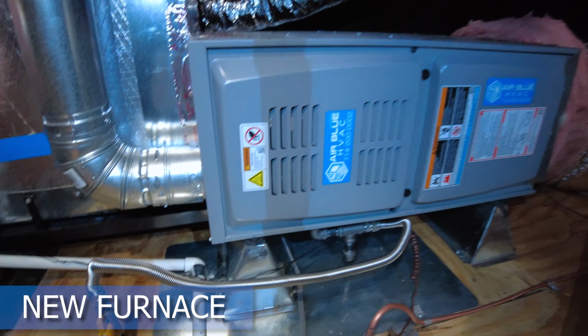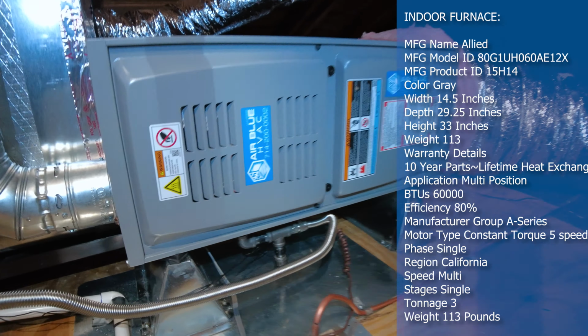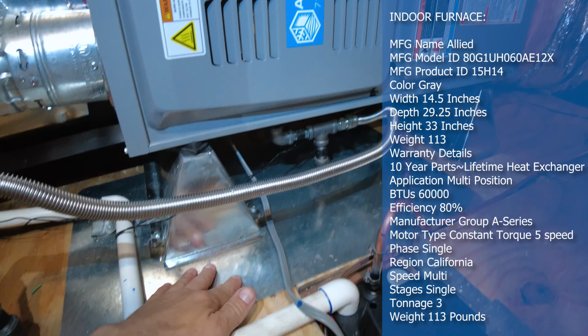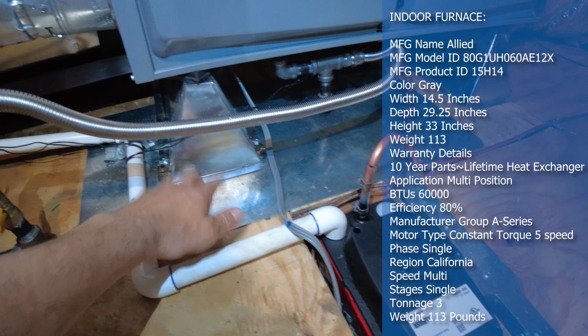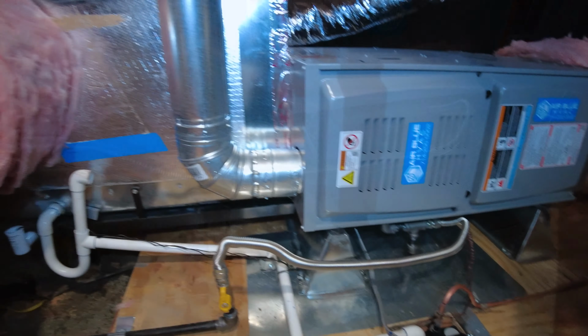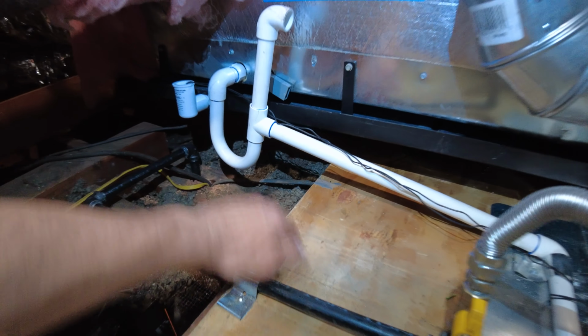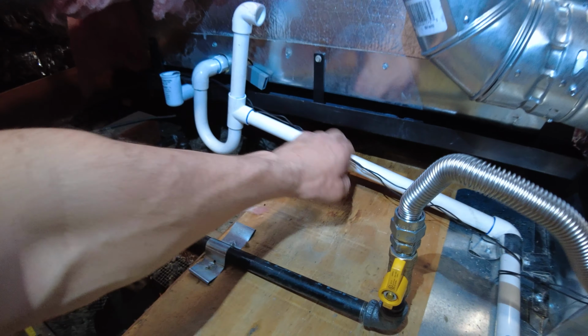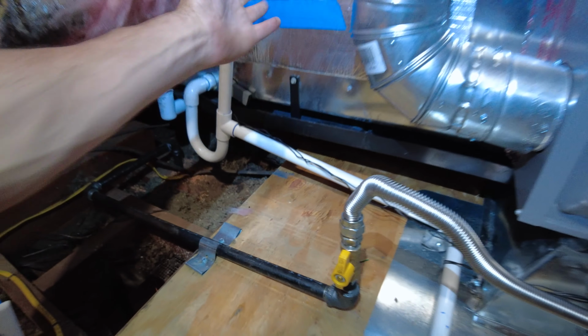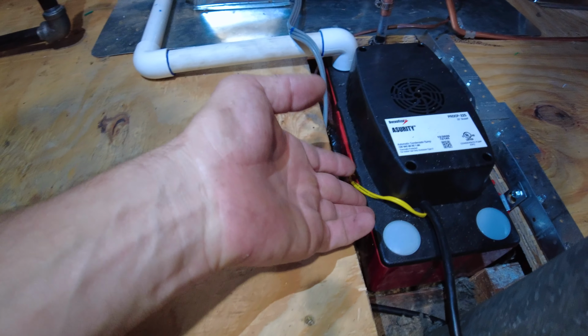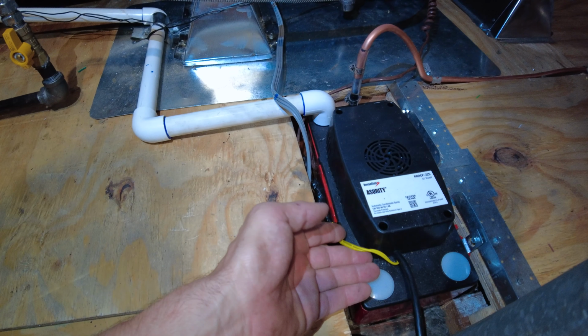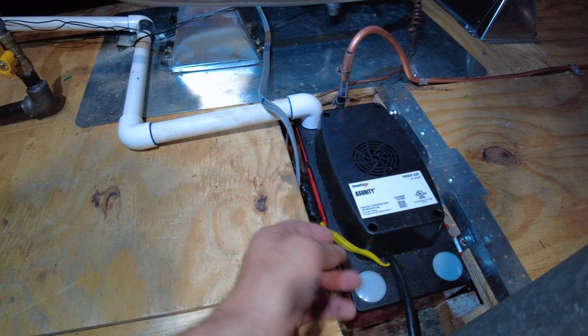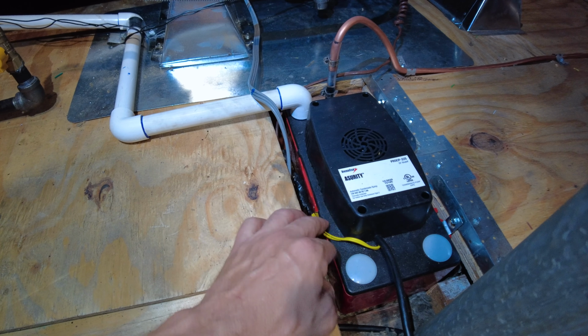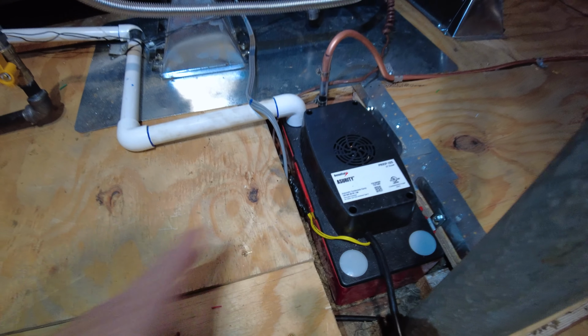This is our new furnace. We relocated it from the closet. The new furnace stands are metal. We put some sheet metal under the burners. We put rubber pads, a new evaporative coil, a secondary drain pan, and an SS2 water sensor in case the drain line gets clogged or in case the coil gets damaged. Also the condensate pump takes the water and drains it down into the washer drain, and the pump is wired as well, so if the pump fails, it's going to stop your AC unit from running.